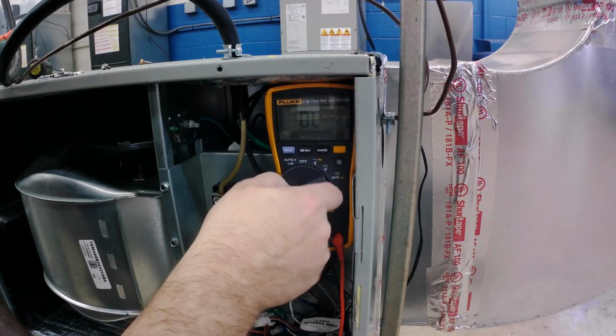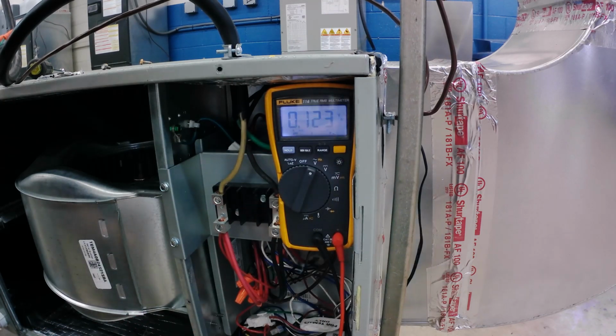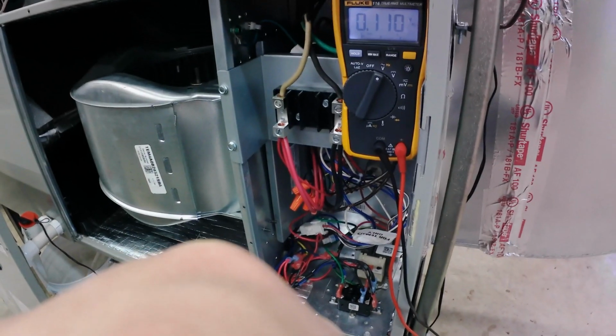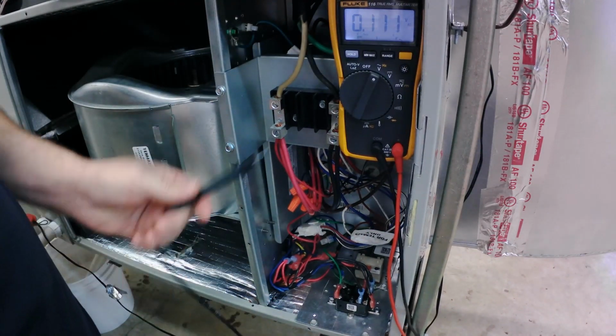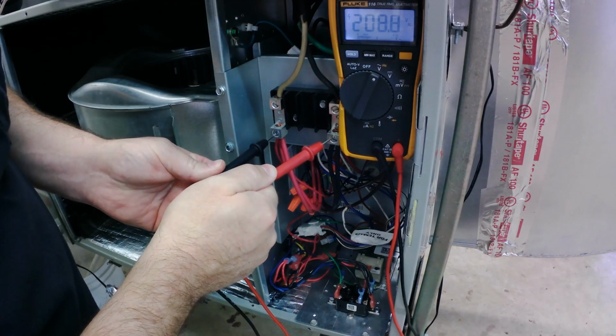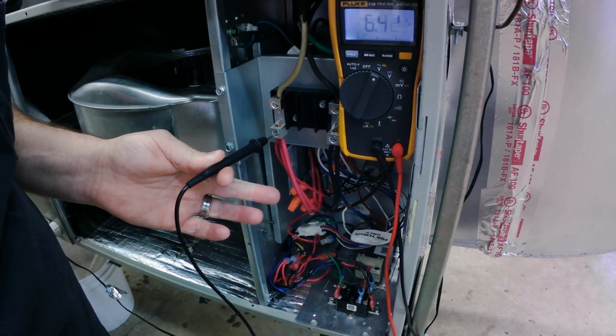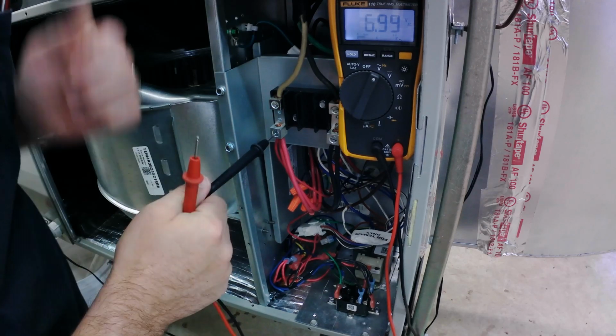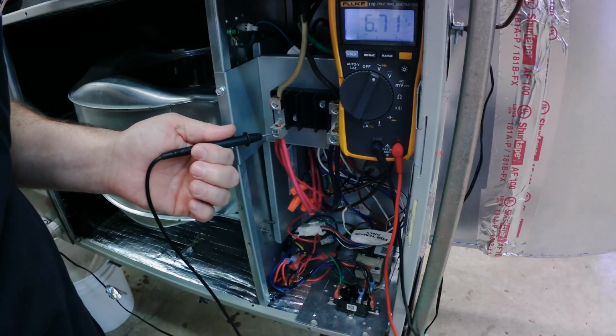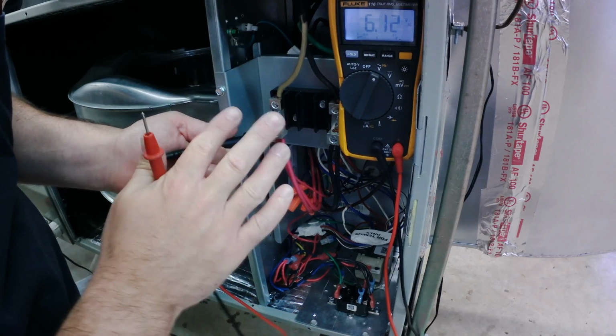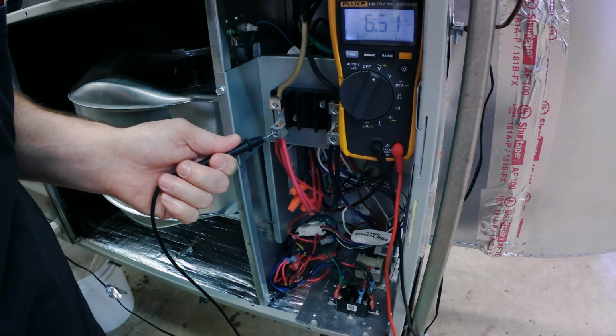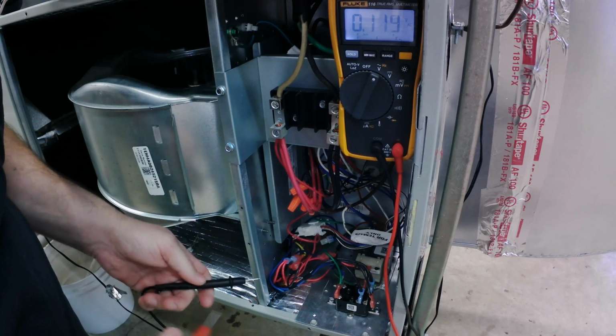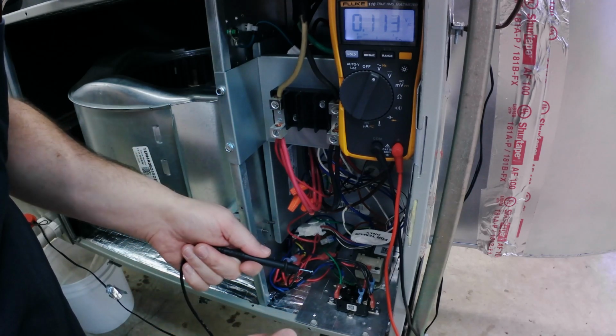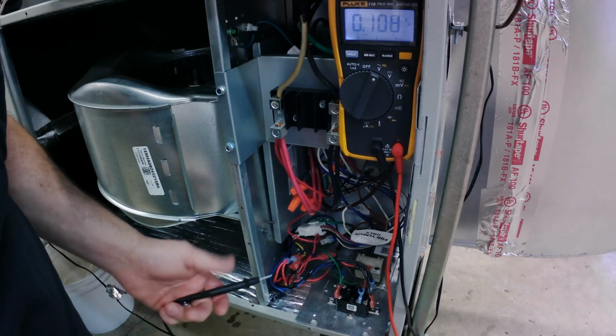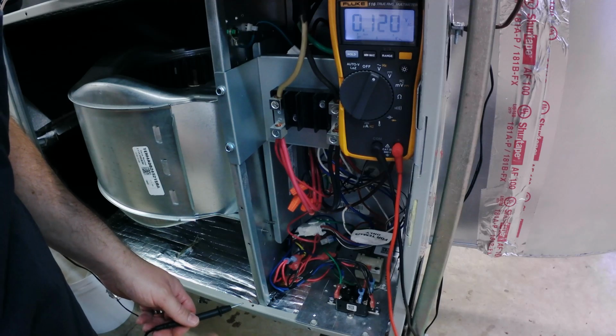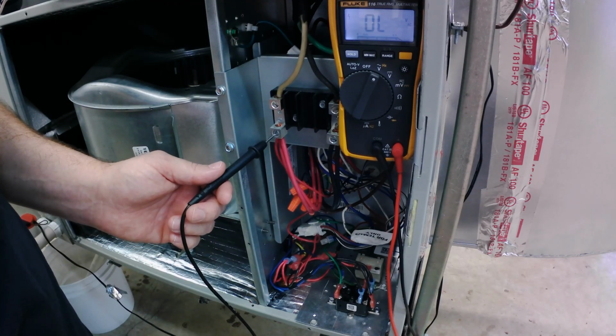So what I would do then is go back to volts on my meter. All right, let me pan you back. I would go to volts on my meter and check my air handler voltage. And I've got 208 in this case. Now, if you've seen any video I've done, like the high voltage hopscotch and even hopscotch with the low voltage, this is my terminal block, this is my power, it's a good source, and I'm always going to reference here. I think what messes a lot of guys up about switches is until you're mentally ready for it as a technician, you can check any terminal you want. Your meter's just going to tell you the difference in the voltage. But if you don't know what to expect, then this hopscotch thing is probably the best way to do this.